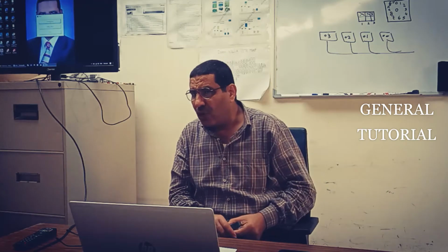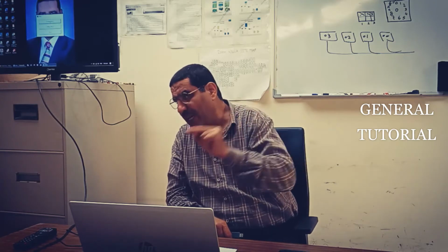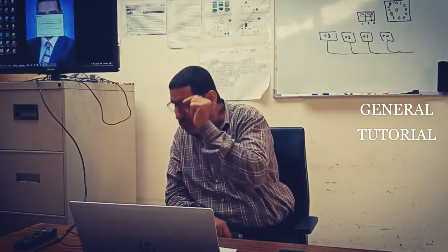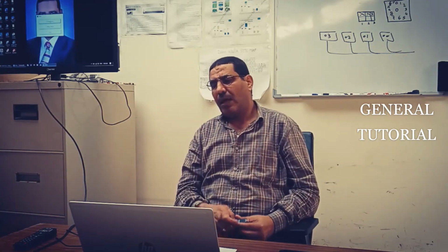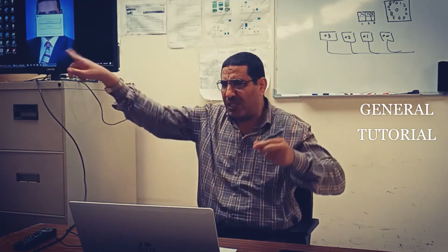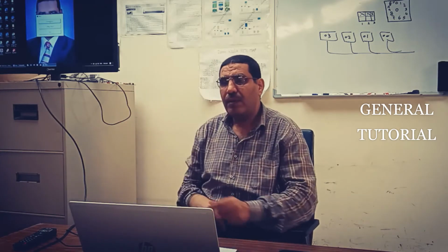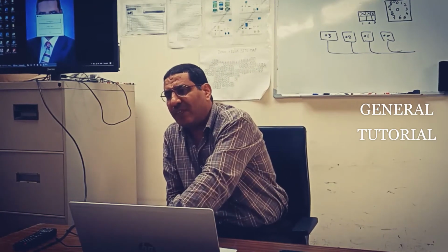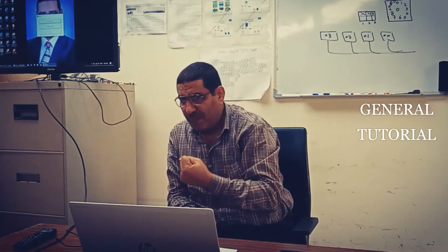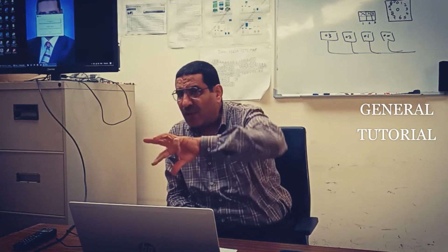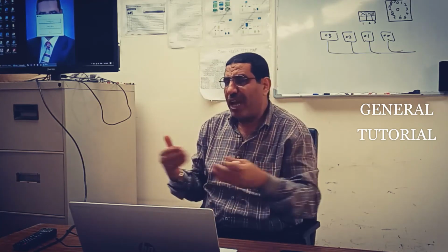If I connect from indoor, I have to connect at X1, X2 from indoor. Outdoor, X1, X2 the same, or Z1, Z2. Understand? I connect here, I put the plug and connect the wire to the system, and put this one here. I have the key and the converter. What's the meaning of converter? It means it receives data from the system and converts the data to the computer. Okay? I connect to the system.